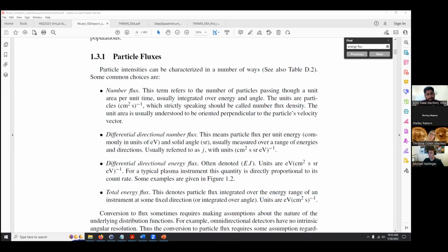And then I will just throw this in because somebody asked if the geometry factor changes with time in terms of aging, and technically no, but I will say that the instrument on ACE, which is CIS, which I talked about, had strips on 2 sides of the detectors. Those strips are independently read out, so you can get the exact location, or pretty much a pixel, of where the particle went through on the detector. We've actually had certain strips go noisy, and so we've turned them off. And so effectively that part of the detector is now dead, and that will actually change your geometry factor.